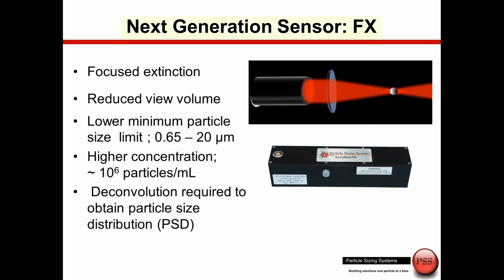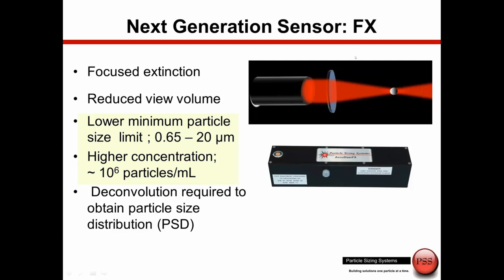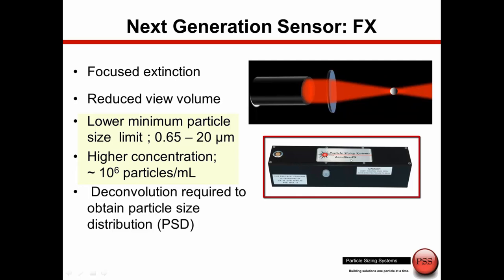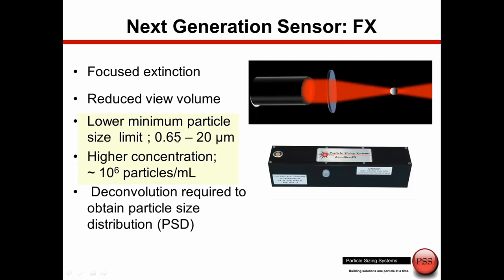The next advancement with the sensors was to focus the laser beam. By focusing the laser beam we accomplish two things: we increase the intensity, and we also essentially reduce the inspection zone. When we reduce the inspection zone we can work at higher concentrations. Using a focused laser beam with an extinction detector, this is the AccuSizer FX sensor, which has a dynamic range of 0.65 to 20 microns but has the ability to work at much higher concentrations up to the order of a million particles per ml.